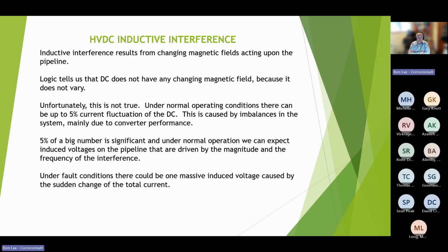And the conductor doesn't care where the interference comes from. The pipeline couldn't care less. But if it gets a magnetic field changing around it, it will induce a voltage in it. And it might only be 5%, but 5% of a big number is still a lot. And with a pipeline, we're in the situation where we have a very narrow band of acceptable voltages on our pipelines, which the standards prescribe for us.